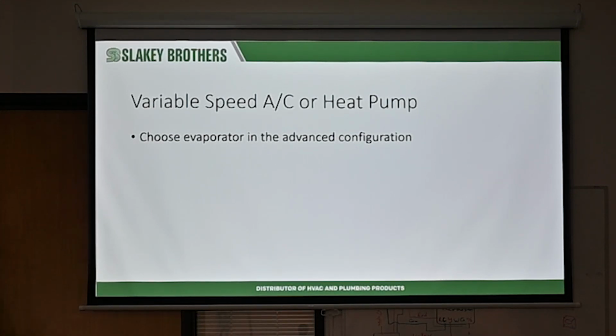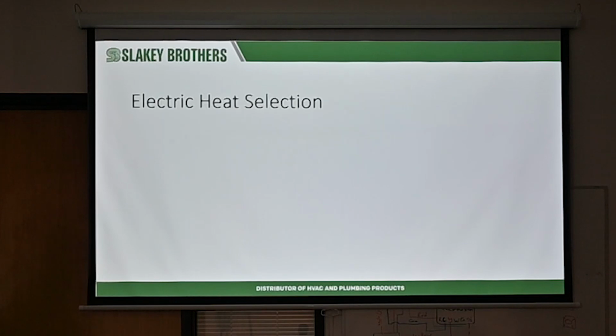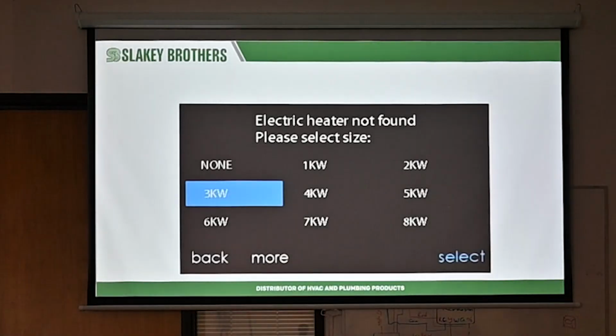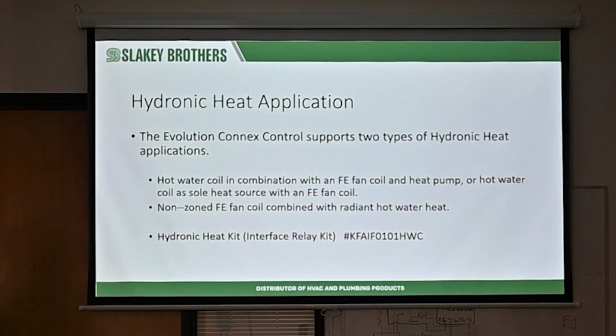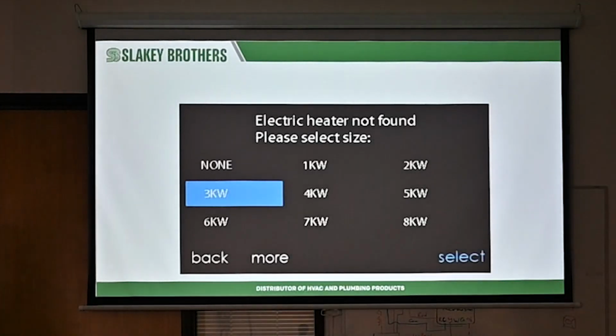If it is an ADP coil, for whatever reason, if the ADP coil matches up to be more efficient than a Bryant coil, there's no ADP coil in there. You're going to have to just fudge it and put a fake number in there, and then just do your own math of how much approximately to add, check the charge, and go at it from there. Electric heat, if it's a heat pump. Again, we're gonna breeze through some of this stuff because it's pretty basic.